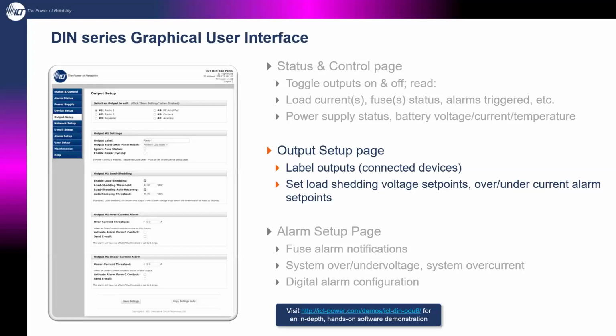Load shedding, as I mentioned before: at what value do we start dropping off some of these devices to ensure your critical loads remain up and running as long as possible? You can set this for each individual device, including the recovery threshold voltage, what voltage we drop it off at, what voltage we turn it back on at, and what state it comes back in.